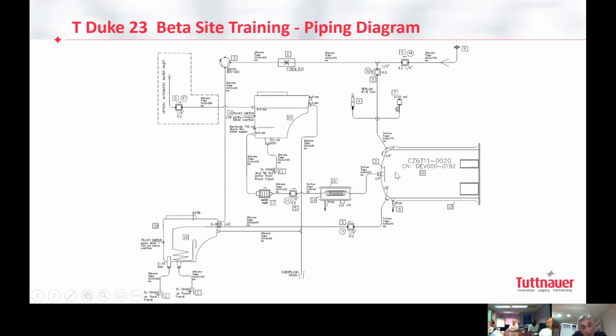Then it reached the pressure we set, because all our parameters are values that we will see later on. And once it reached the pressure, for example, in PSI, like 10 PSIG, then it stopped. This one gets closed, the pump stops. Now we will not go for the vacuum directly. Since there is pressure inside the chamber, before I start, I don't want the steam pressure, which comes via the pump to the waste, to affect the pump.